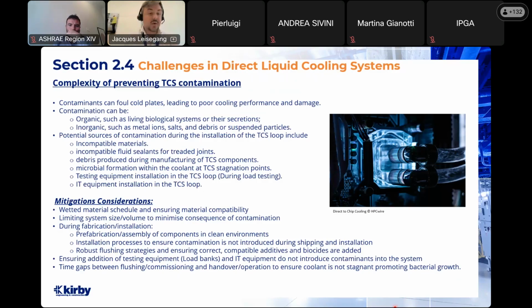When testing equipment like load banks is introduced, and when the IT equipment is introduced, we need to ensure that that does not introduce contaminants into the system. Consider time gaps between flushing, commissioning, and handover to operation. We need to ensure that the coolant is not stagnant during those periods and that there's continuous circulation and monitoring of the water quality during the whole process.